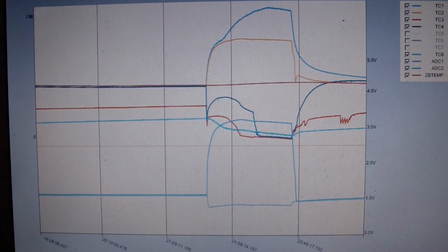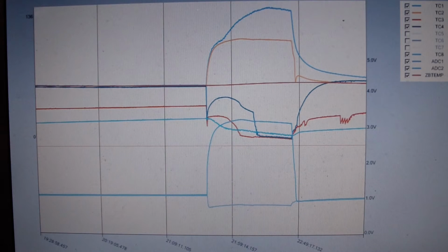The reason it rises so rapidly probably has a lot to do with the fact that once the temperature drops really quickly, we get a heat flux from the copper tubing that's encasing all that refrigerant. So it starts to warm it and ultimately superheat it. It takes a little bit of time until the pressure in the high side rises to the point where we regain our liquid plug that we lost during the off time. We have a fixed bore capillary tube, so it doesn't have really any control other than just the natural characteristics of a capillary tube in a refrigeration system.